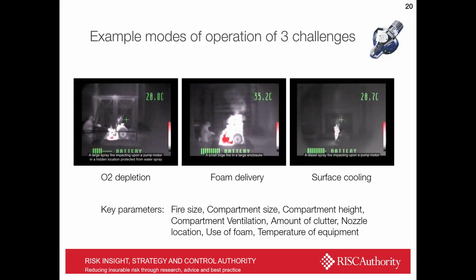In the middle one, this is a small fire, but in this case, the ventilation of the enclosure is such that the small fire will not go out by itself. But this particular Watermist system we enhanced with foam, so that gets taken care of by foam. The one on the right-hand side is slightly more surprising. Again, this is a spray fire onto a hot surface, onto the side of a pump, to simulate a diesel generator catching fire, but with a fuel leak onto it.